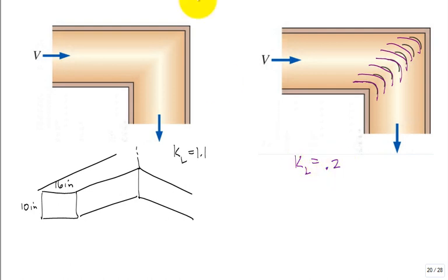You might think, well, what's the big deal? It doesn't look like it's that significant, but it can be. If you're really interested in moving as much air in a small area as possible, it's going to go as fast as you can get it to go without making a lot of noise. And when it goes fast, it can have significant pressure drops because of frictional losses. So you want to help it by putting in turning vanes or making smooth transitions.